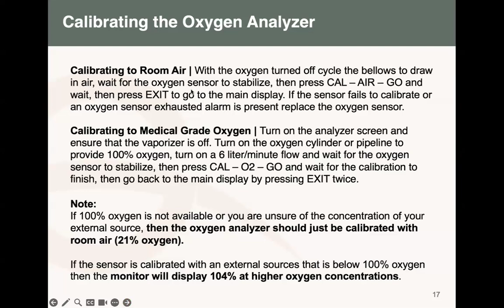So the procedure is the same, simple. You make sure that you bag. If you have used the machine with oxygen, or when you switch on and found it maybe at 65, you bag until you reach the lowest level, which most of course will be 20%. That's where you calibrate. And while bagging, make sure oxygen is closed, so it's only air coming in while the oxygen flow is closed. Once you attain the lower percentage, most likely within 1, you calibrate: cal, air, go, and then you exit. Next.